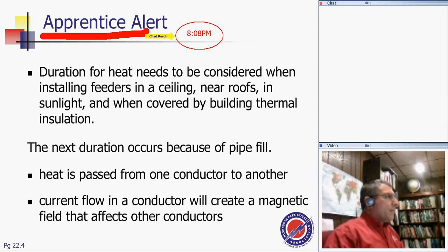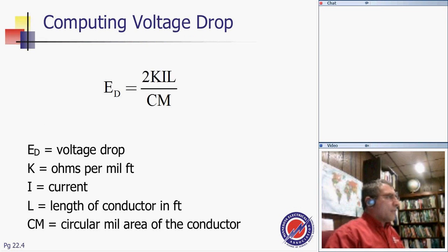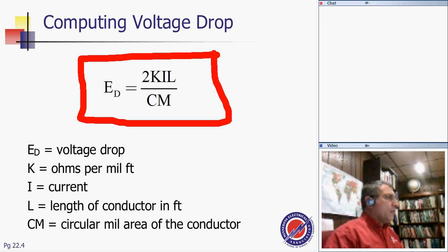Okay, another thing you have to pay attention to is that when you put conductors, you have to put them in close proximity with each other, because that's how you can reduce the impedance of these conductors. And we'll get to one in a second here. Voltage drop. This is the formula that we were talking about, guys. The voltage drop, E, equals 2 KIL over CM.